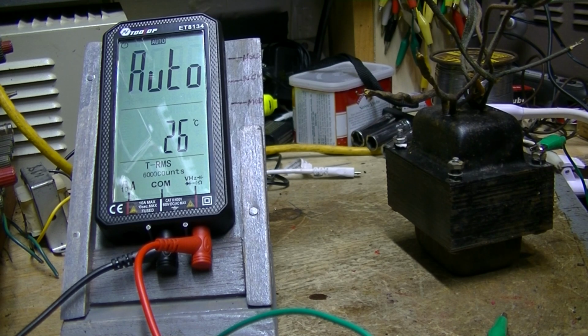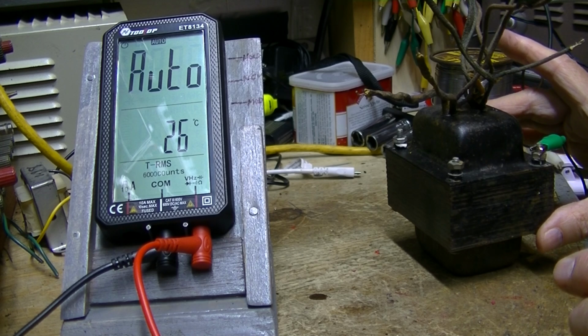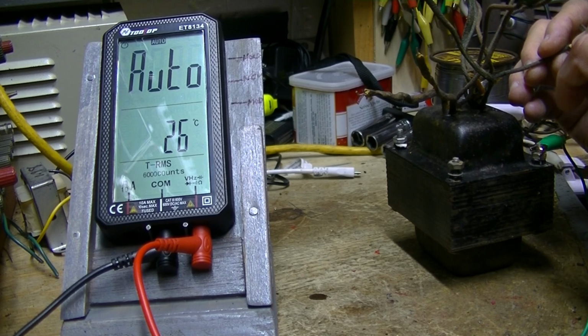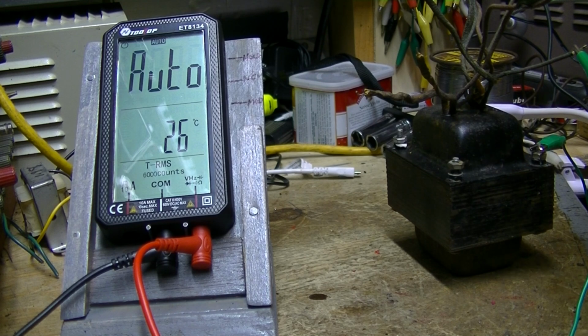We're using clip leads, it's more reliable than trying to hold it on. We've got the lead grounded, I tightened up the nut here so we get a good ground. So we've got one side of the ohm meter to the frame of the transformer, and we're going to test the primary here first for ohms.